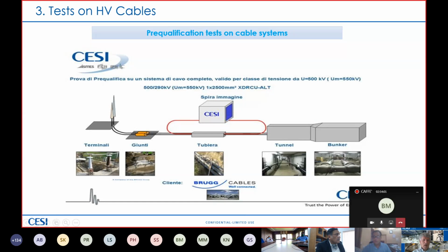Here you have an example of a tunnel. This is a very special tunnel we used in Milan for the first time ever in the early 90s to test the first 400 kV XLPE cable system ever tested in history, for the BEWAG project. BEWAG was the Berlin utilities. So this is a very special tunnel where we have two main sections: one real tunnel plus a bunker where we can install the back-to-back situation. For example, here you can see we have a back-to-back in horizontal connection instead of a single one.